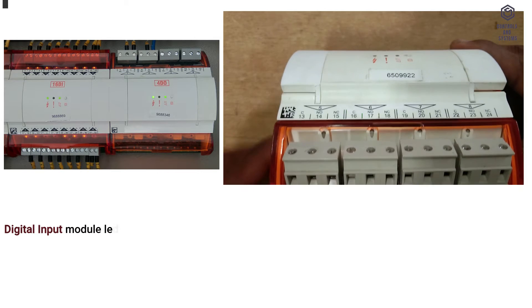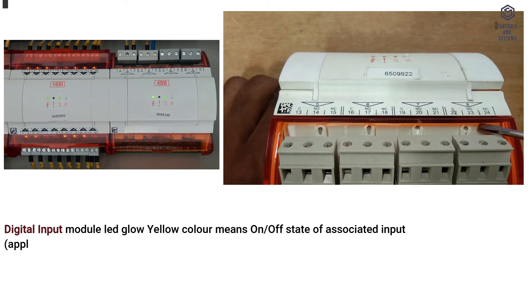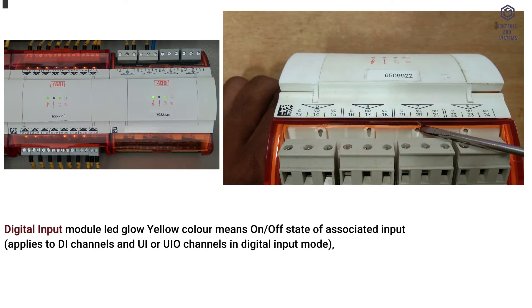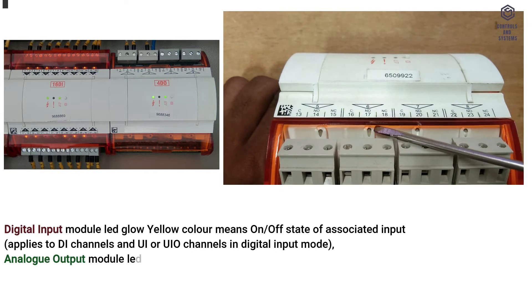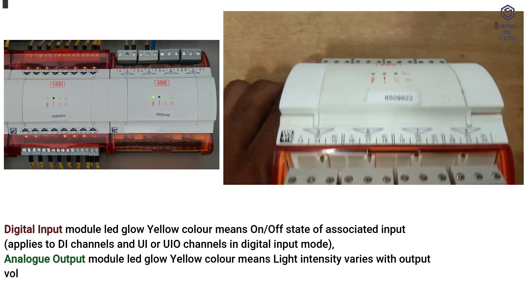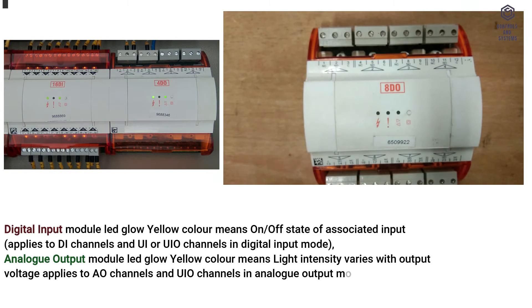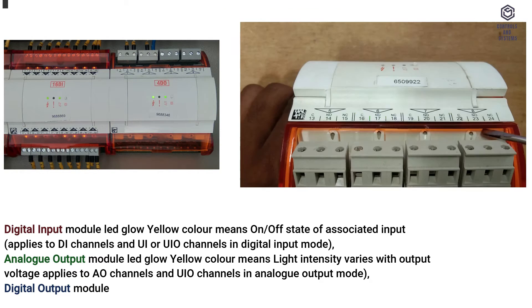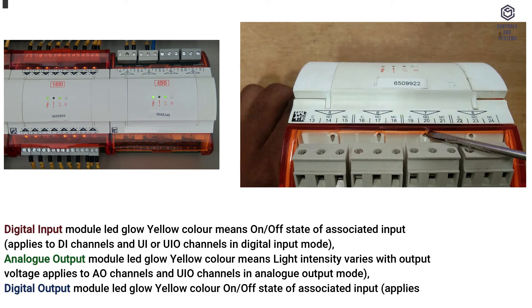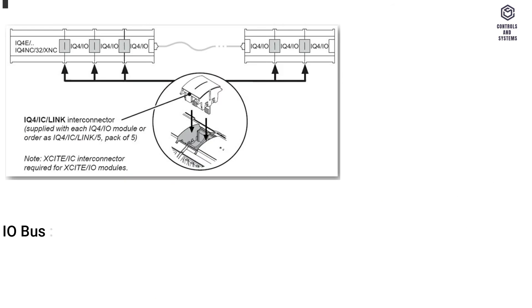Digital input module LED glows yellow — indicates on/off state of the associated input; applies to DI channels and UI or UIO channels in digital input mode. Analog output module LED glows yellow — light intensity varies with output voltage; applies to AO channels and UIO channels in analog output mode. Digital relay output module LED glows yellow — indicates on/off state of the associated output; applies to DO channels only.